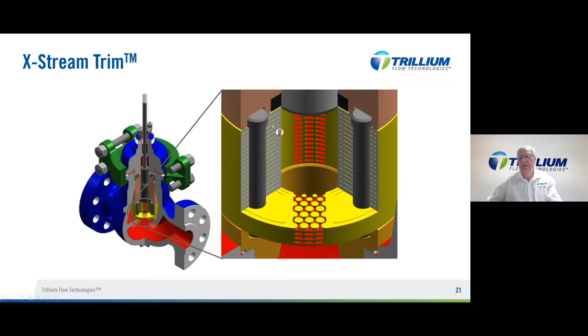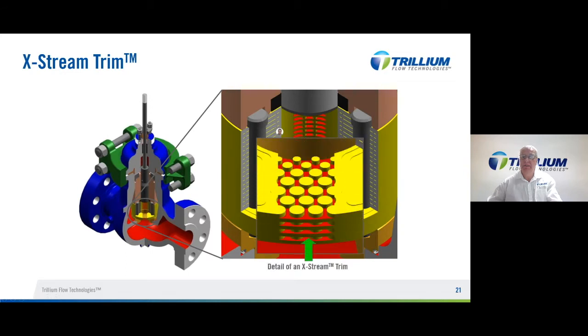So you might say, what's the solution for high pressure drops, high pressure reduction through the valve trim itself? And the answer is essentially our X-Stream Trim. The X-Stream Trim doesn't have 90-degree corners. Instead, it has a smoother flow profile that lets any debris that can get into the trim wash through the trim and exit through into the bore where the plug would be located.